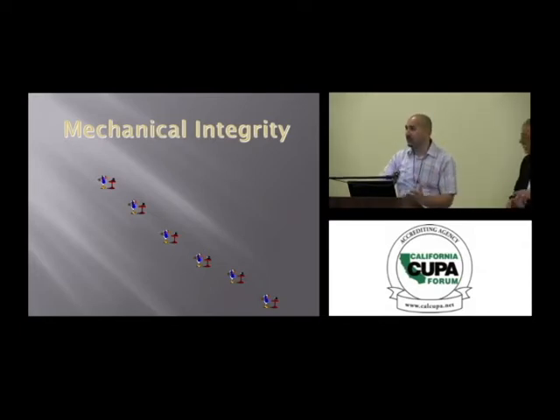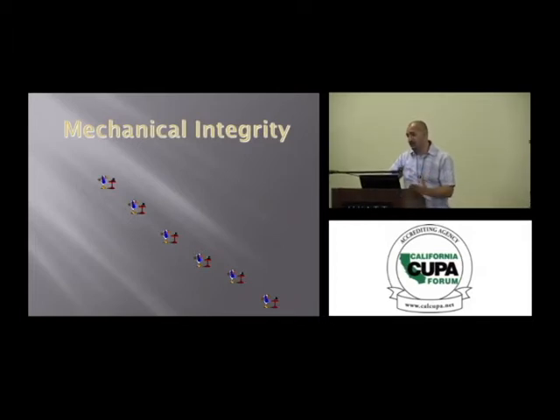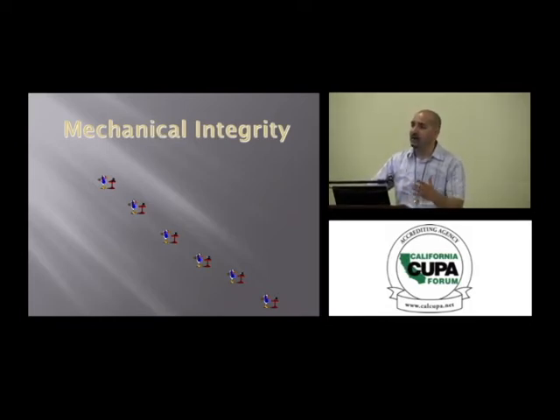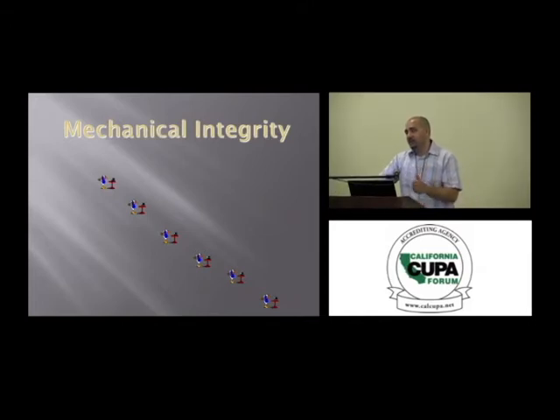Let's say when I'm doing my inspection, I come across relief valves that have not been replaced within the 5-year period. I always bring up, and I say, if you care, we can size the relief valves for you, if you care to eventually vent them up to the atmosphere or put them into an absorption tank. I think it's a good idea with the facilities that are within the city.